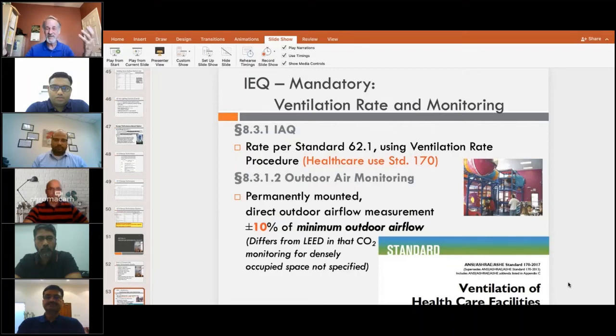And we've seen some of that right here, in the past couple of years with the pandemic, that has really brought that into focus. And then also looking at this idea of outdoor air monitoring. I mentioned that just a minute or two ago. What it specifies is that on the outdoor air intake for an air handling unit for a building, you have a permanently mounted measurement device that has the ability to detect within plus or minus 10% of the minimum airflow how much is coming in.